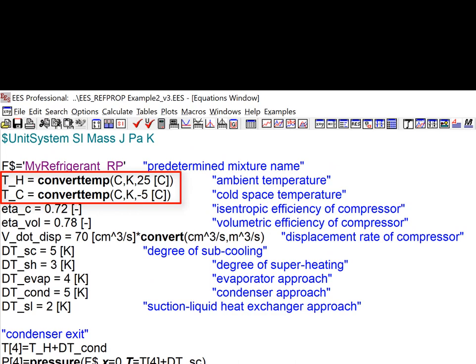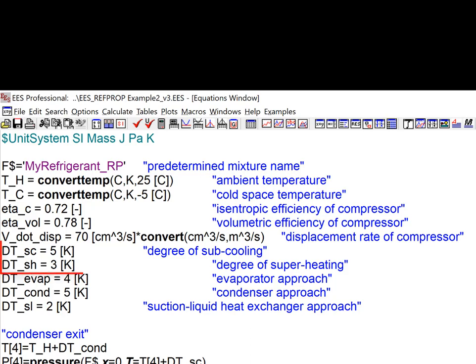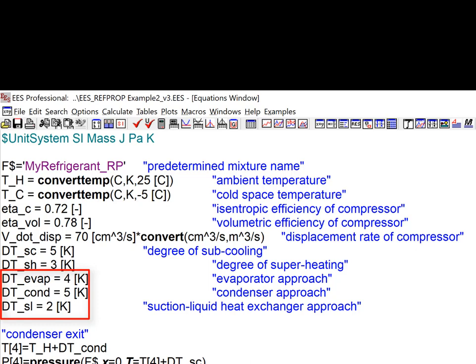The displacement rate of the compressor is 70 cc's per second. It has a volumetric efficiency of 78% and an isentropic efficiency of 72%. The cycle has some superheat and subcool, so 3 degrees and 5 degrees Celsius, respectively. And then the three heat exchangers all have some approach temperature difference. The condenser, evaporator, and suction liquid heat exchangers have approach temperature differences of 5 degrees Celsius, 4 degrees Celsius, and 2 degrees Celsius, respectively. And these are the input parameters then entered in EES.